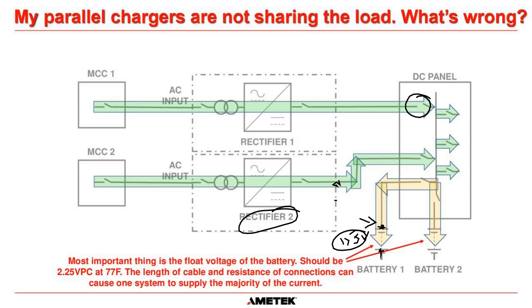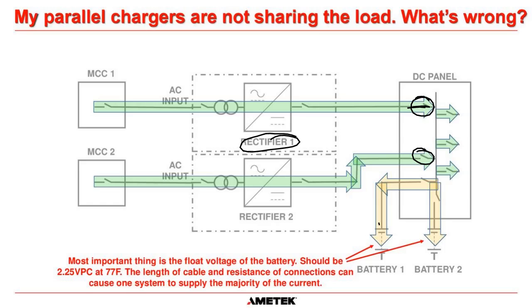Okay? So we know that rectifier 2, through all the cable drops and everything, is putting 135 volts out to the battery. Then I would close this breaker here, and then open this breaker here, and I would set charger 1 so we have 135 volts at the battery terminals. That means with both of these chargers, they are putting out 135 volts to the battery terminals.